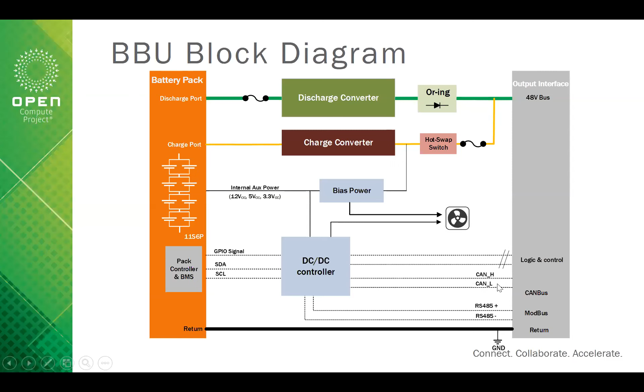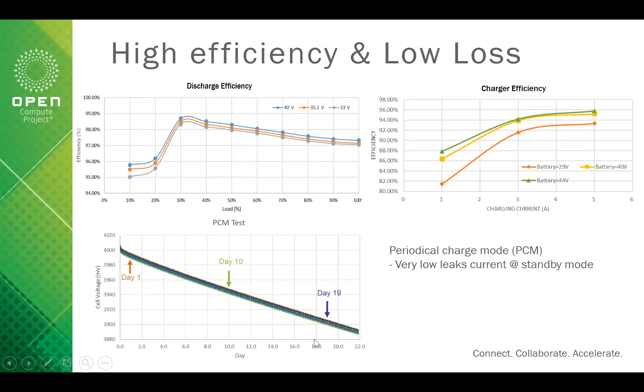This page is showing our charge and discharge testing efficiency. You can see we can achieve more than 98% for the discharging mode, and something like 90% for the charging mode. When we have the battery in the standby mode, the cell, if fully charged, is at 4 volt, and in standby mode the battery voltage can stay at 3.9 volt for more than 90 days.